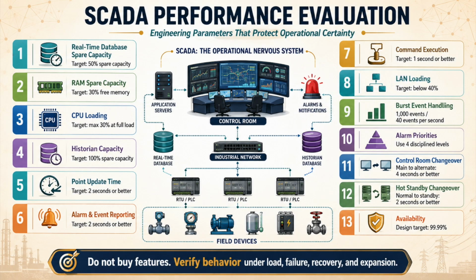The 14th engineering parameter is alarm priority discipline, because 4 priority levels such as low, high, emergency, and journal are usually enough. Too many levels create confusion, too few create poor differentiation, and alarm priority must be based on consequence, urgency, and required operator response time, not equipment importance alone. Every alarm should have cause, consequence, operator action, and allowable response time. And if an event does not require operator action, it should not behave like an alarm. Emergency alarms must not compete with advisory messages, journal events must not behave like process alarms, and low-value alarm floods must not bury the few alarms that actually require immediate intervention.